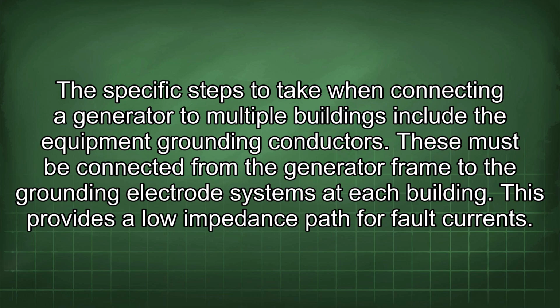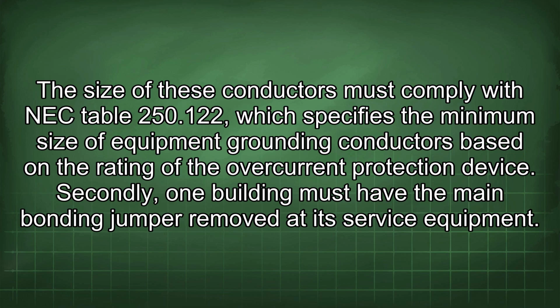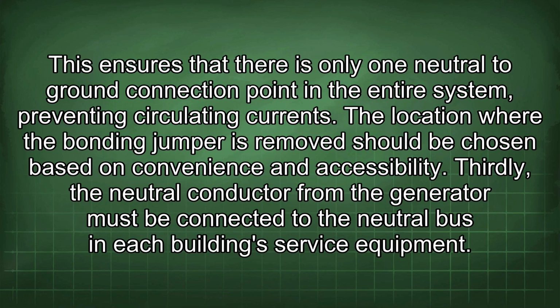Specific steps to take when connecting a generator to multiple buildings include the equipment grounding conductors. These must be connected from the generator frame to the grounding electrode systems at each building. This provides a lower impedance path for fault currents. The size of these conductors must comply with NEC Table 250.122, which specifies the minimum size of equipment grounding conductors based on the rating of the overcurrent protection device. Secondly, one building must have the main bonding jumper removed at its service equipment. This ensures that there is only one neutral to ground connection point in the entire system, preventing circulating currents.